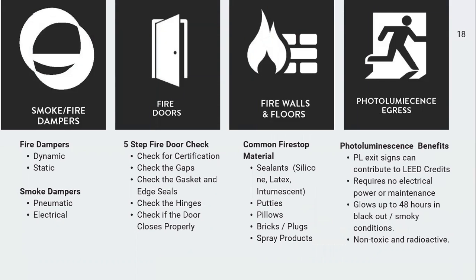Fire dampers are dynamic, or static. Smoke dampers are pneumatic and electrical. And fire doors require a 5-step fire door check. They need to be checked for certification or labeling. They need to be checked for gaps, gaskets, edge seals, hinges, and making sure that the door closes properly as per the code. Firewalls and floors need to be checked for common fire stop material.